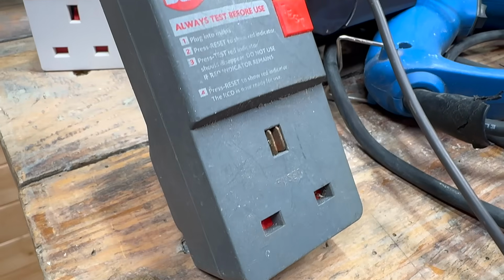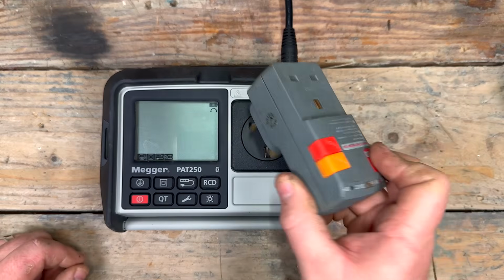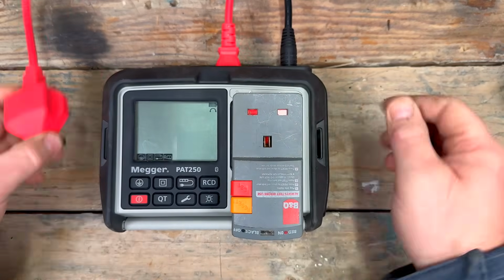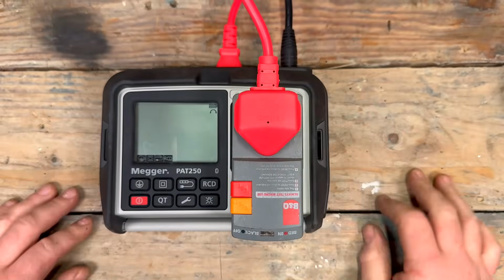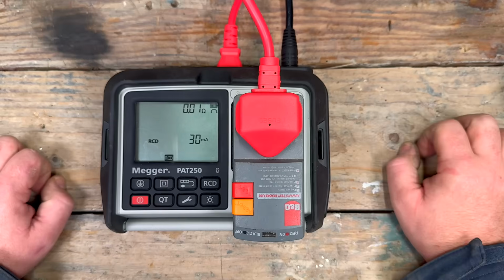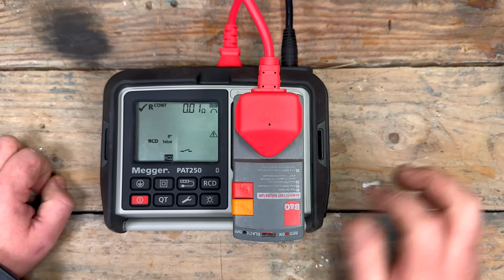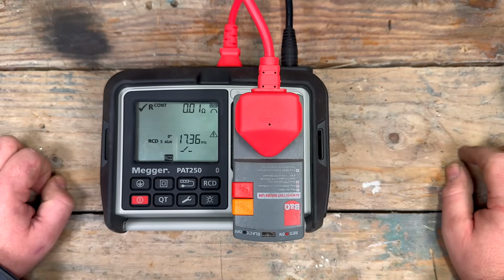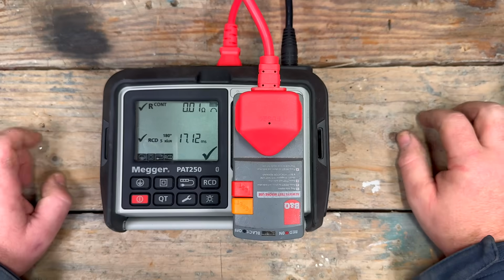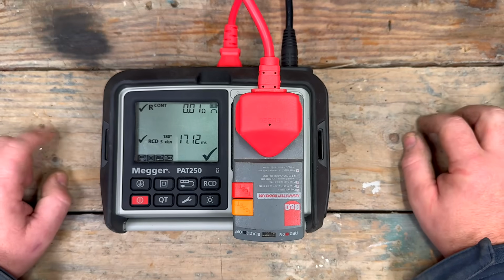Next up, we're testing this RCD plug. We need to ensure that the RCD will trip in the event of an earth fault. To do this, we plug it into the PAT250. We then plug the breakout lead into the RCD plug. The PAT250 does need to be plugged into the mains for this, as it is a live test. The tester will automatically cycle between 0 degrees and 180 degrees of the sine wave, and is going to test at times 1, and times 5. So there we have it.